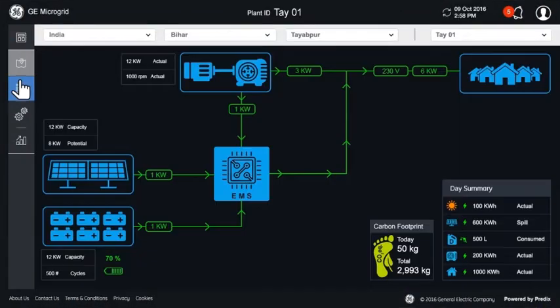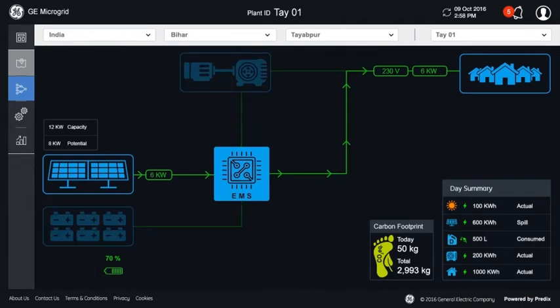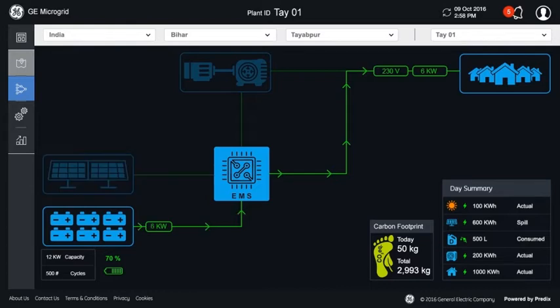The application's plant diagram provides a quick snapshot of the operating condition of the microgrid. During the day, the GE energy management system feeds solar power to the load and stores excess energy in the battery. When solar energy subsides, the battery supplies the load till it reaches a threshold, at which point the diesel generator is switched on.